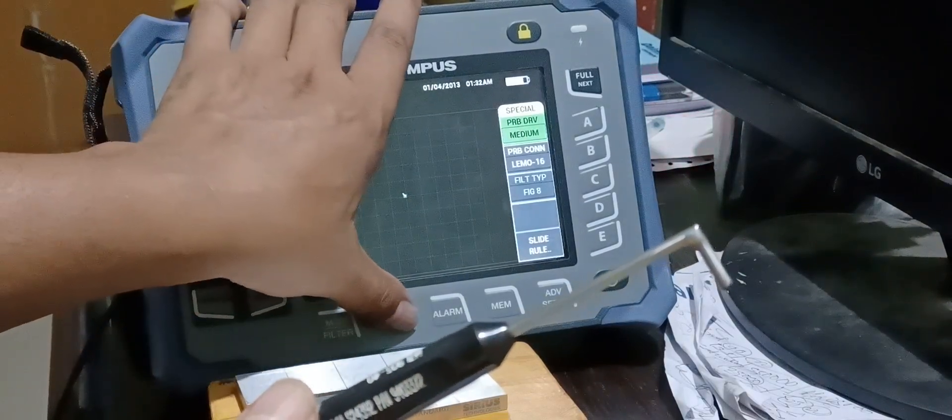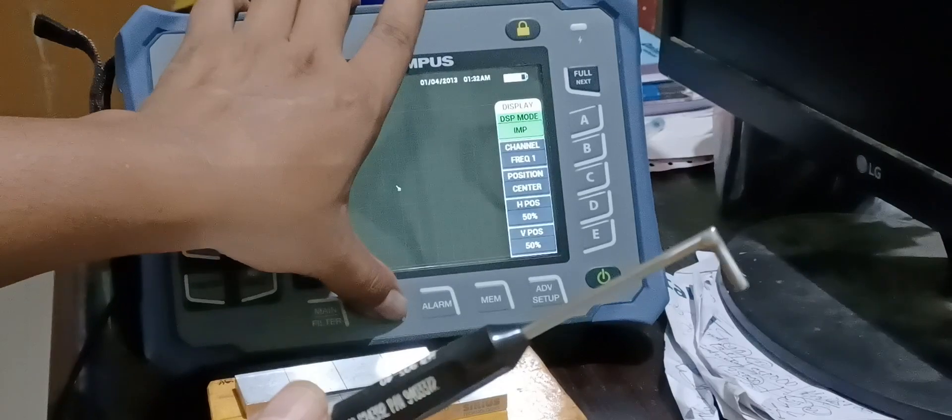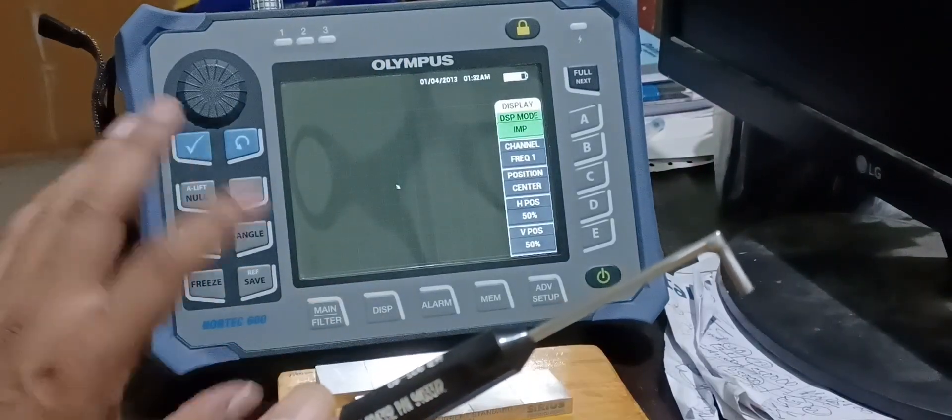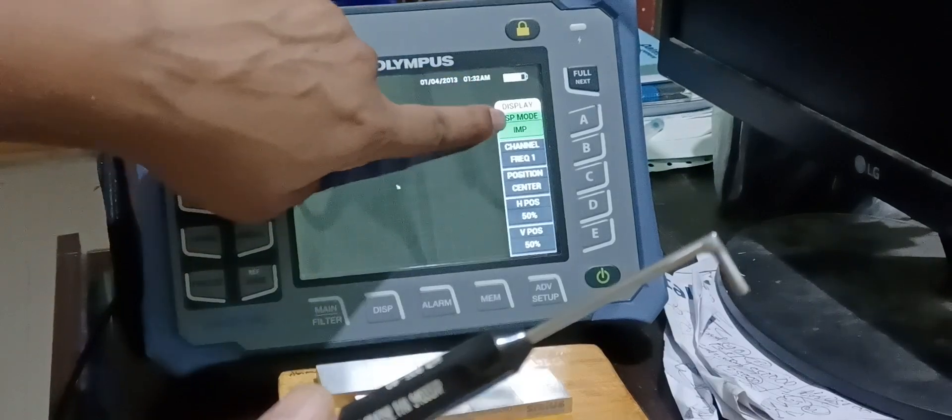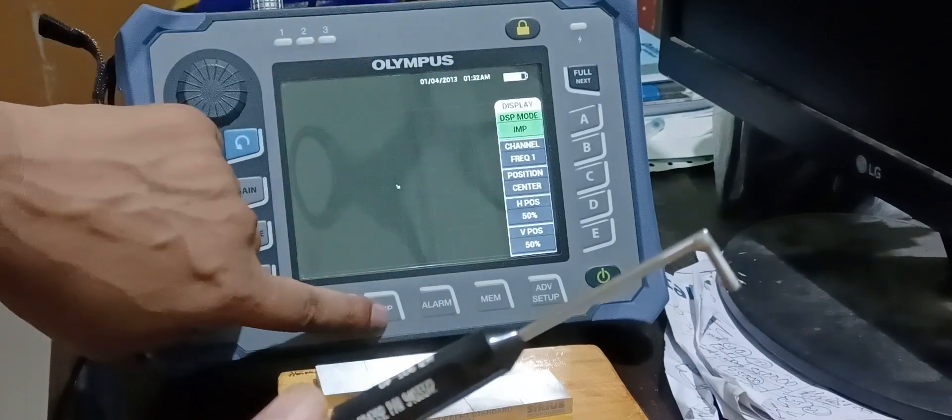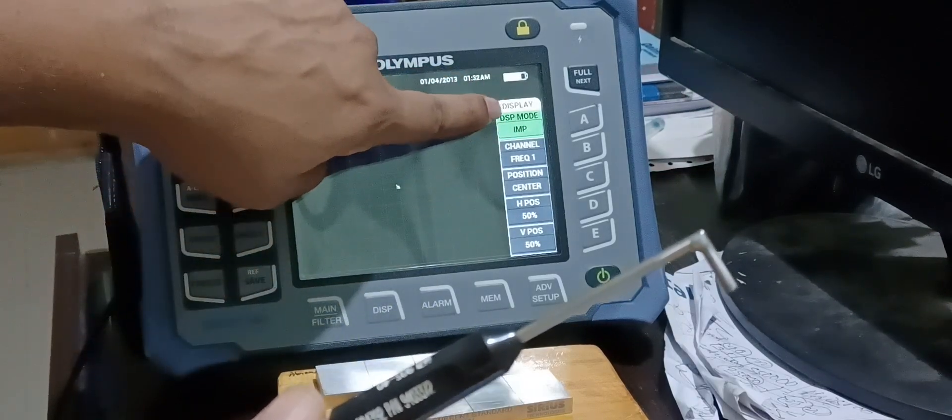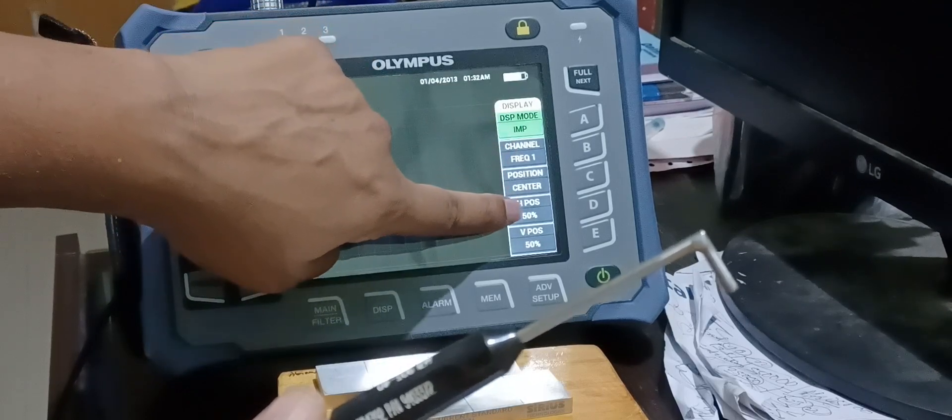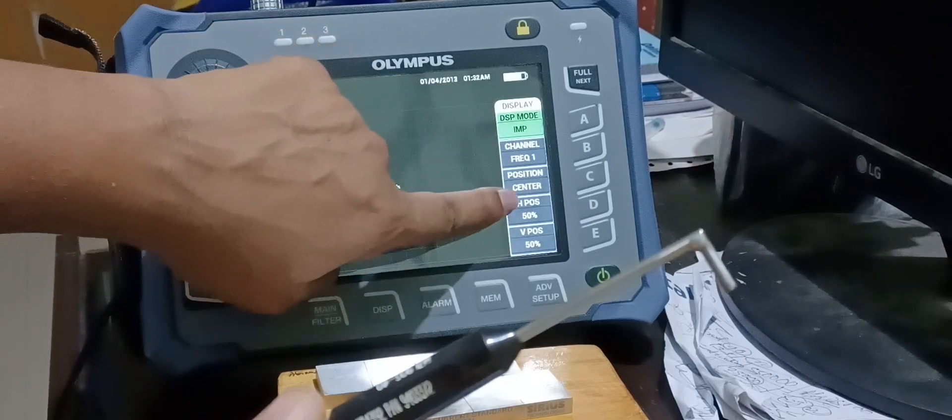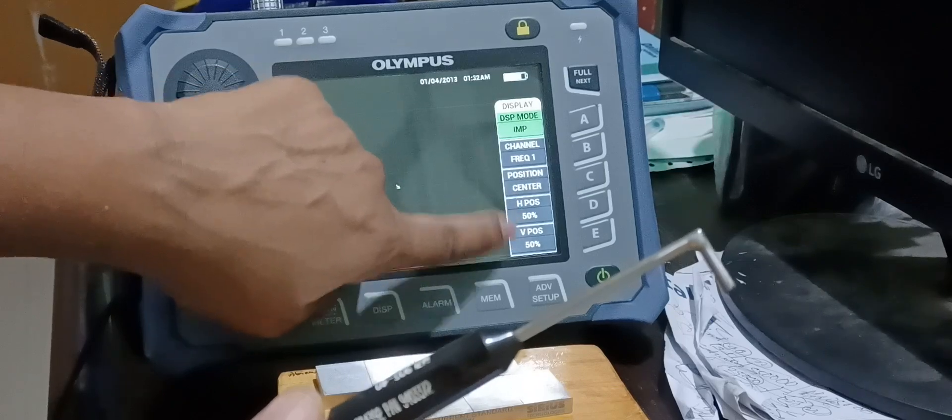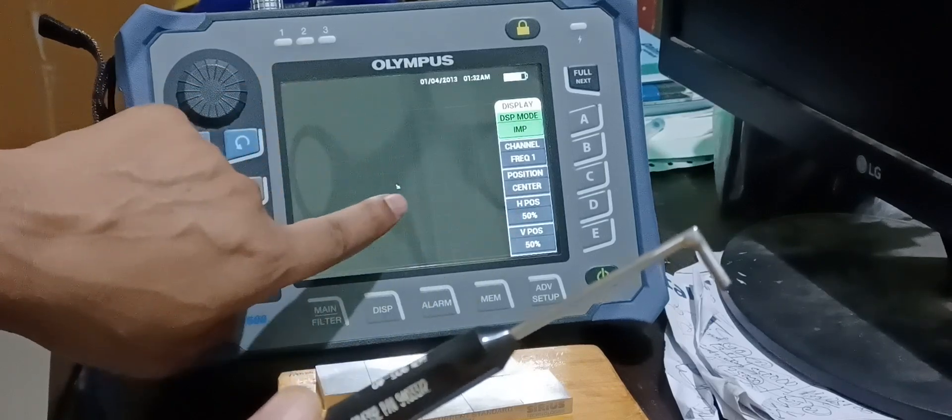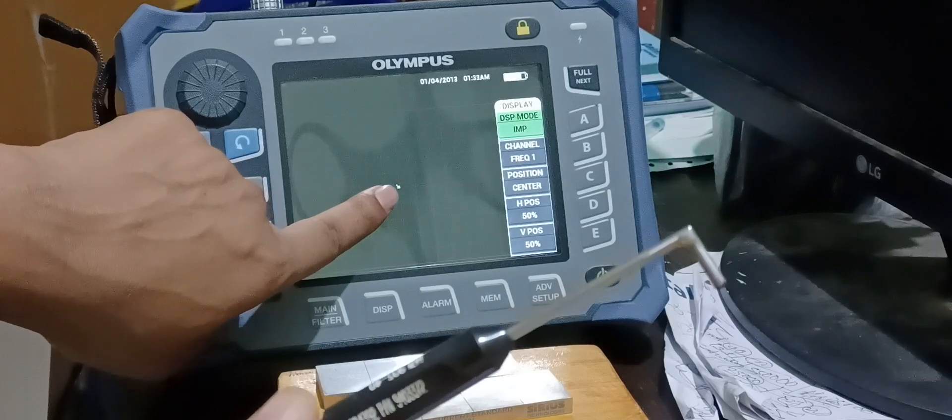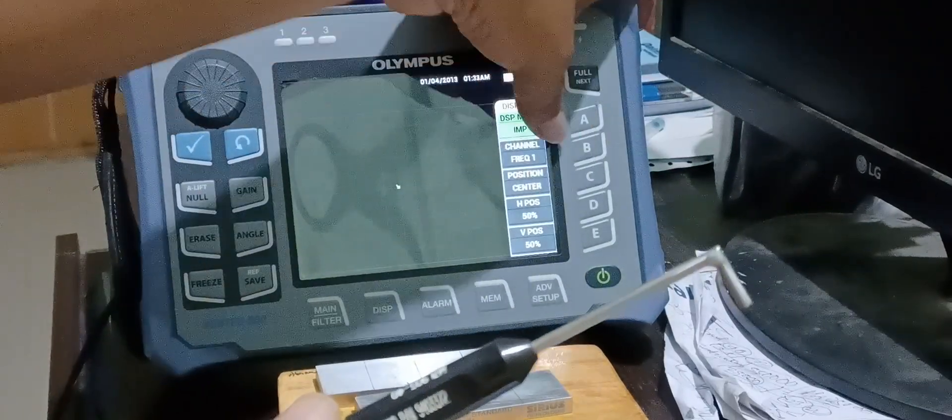Now this is the display. I am pressing display. The second option is display. Now everything starts appearing which is coming under the display menu, like display mode, channel, position, horizontal position and vertical position. Here horizontal position and vertical positions are 50-50. That's why this point is appearing in the screen.